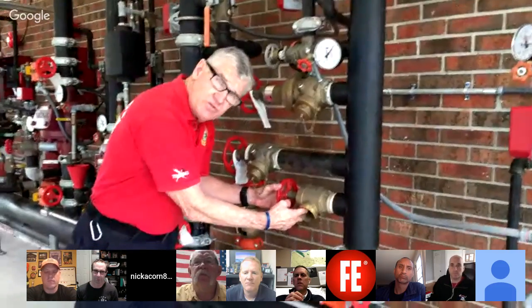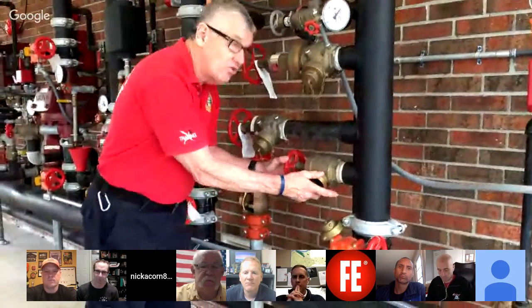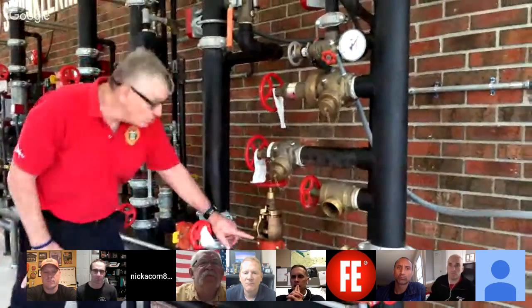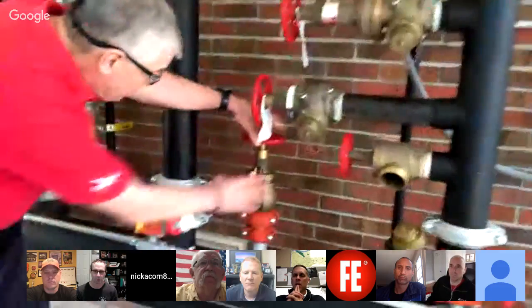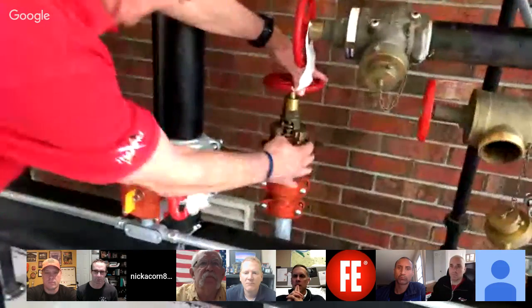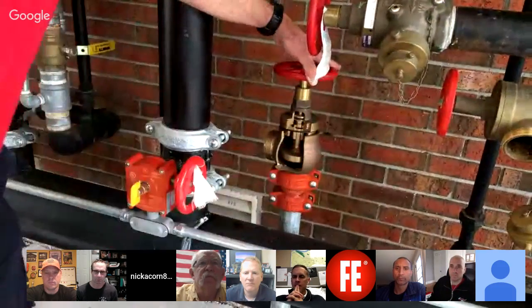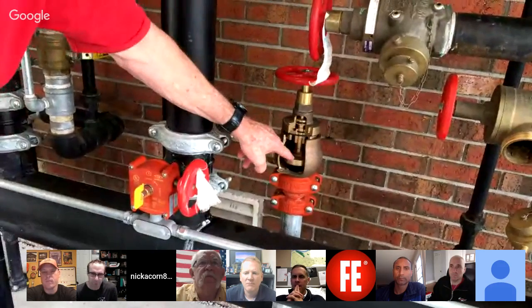If you look in here, I don't know if you can see this, there's threads in the stem. This is a conventional. One way of identifying a pressure reducing valve is that it has a smooth stem, because the valve wheel assembly is not really mechanically connected to the PRV or the floating piston that reacts to changes in downstream pressure.